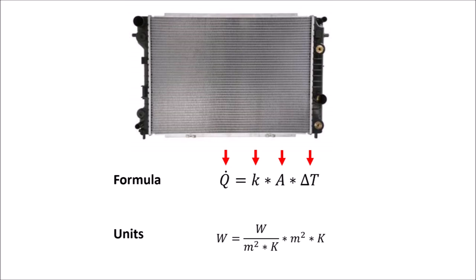Delta T is the temperature difference between water inlet and outlet, and the area is the complete surface area of the radiator. The k factor is an adjustment factor in this formula and tells you how efficient the radiator net is. The higher the better.